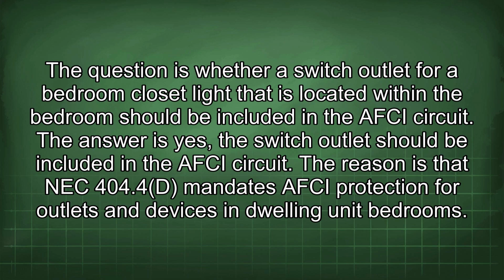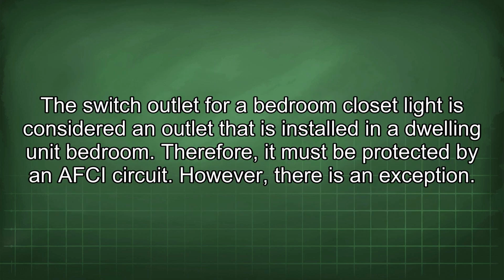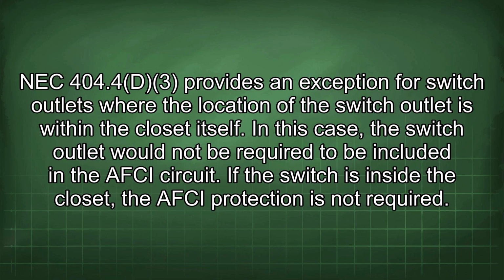The reason is that NEC 404.4D mandates AFCI protection for outlets and devices in dwelling unit bedrooms. The switch outlet for a bedroom closet light is considered an outlet that is installed in a dwelling unit bedroom. Therefore, it must be protected by an AFCI circuit. However, there is an exception. NEC 404.4D3 provides an exception for switch outlets where the location of the switch outlet is within the closet itself. In this case, the switch outlet would not be required to be included in the AFCI circuit. If the switch is inside the closet, the AFCI protection is not required.